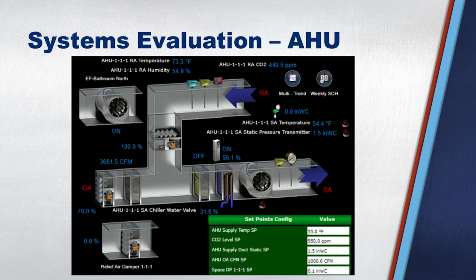Help them. So this is one of the air handling units. A lot of their air handling units actually had a 100% outside air coil. All those valves were just forced open. That's where the low delta T was coming from.